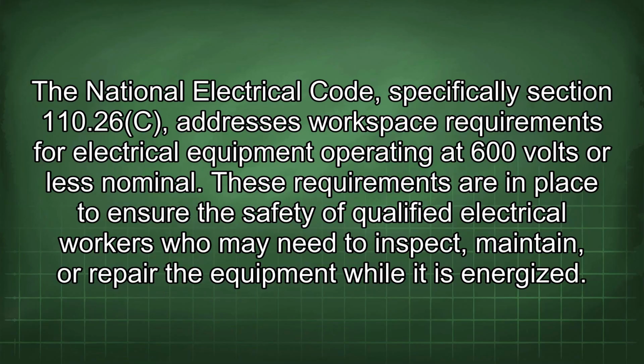The National Electrical Code, specifically Section 110.26(C), addresses workspace requirements for electrical equipment operating at 600 volts or less nominal. These requirements are in place to ensure the safety of qualified electrical workers who may need to inspect, maintain, or repair the equipment while it is energized.